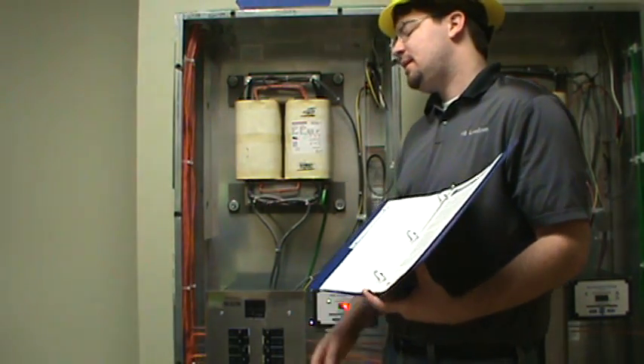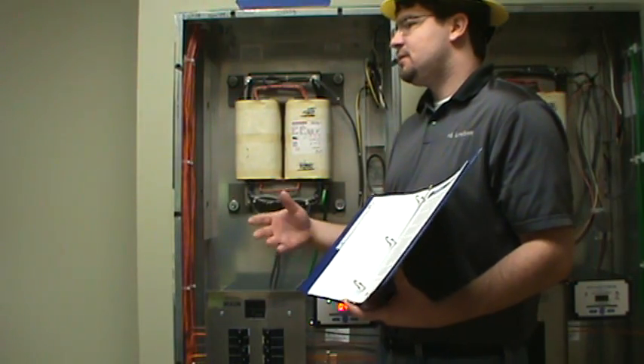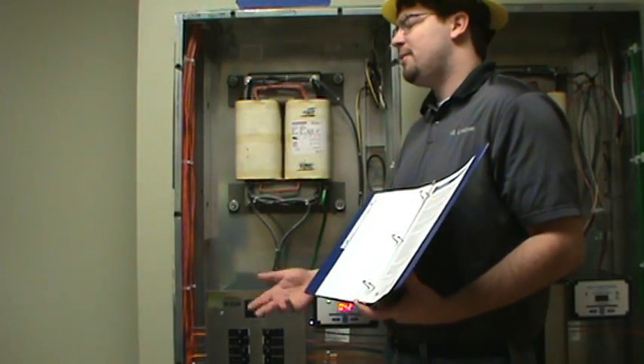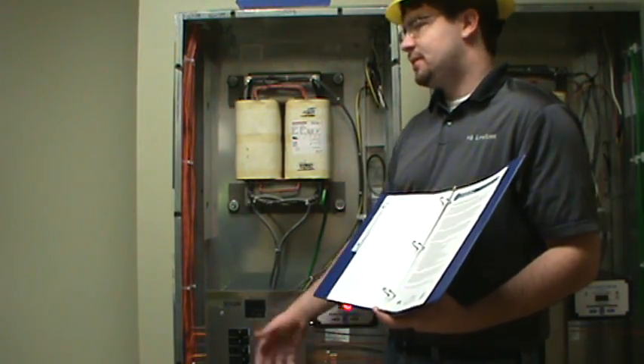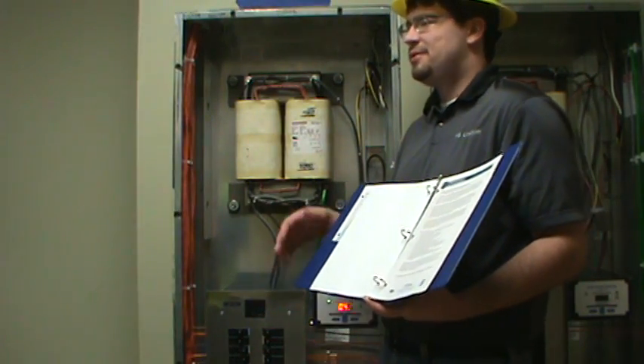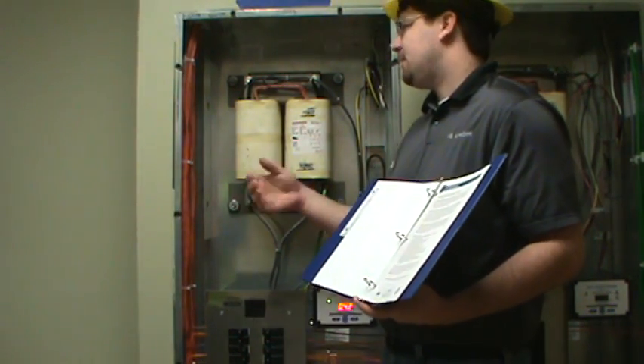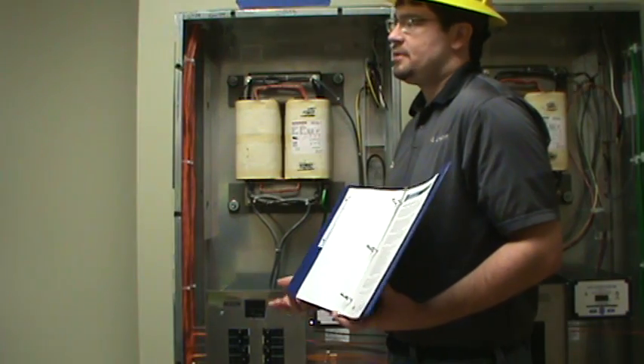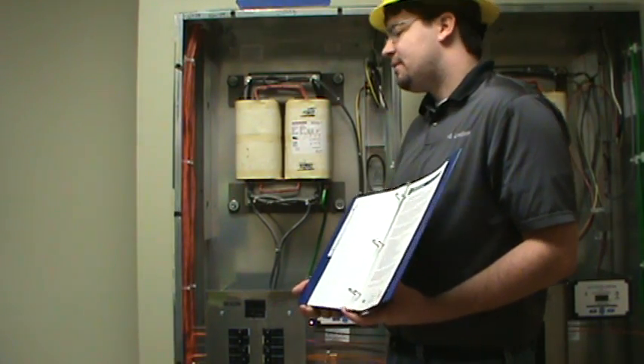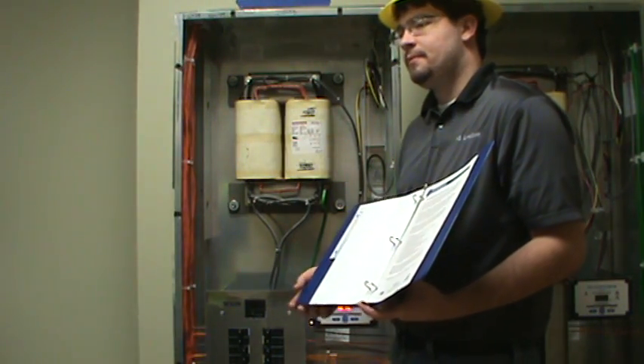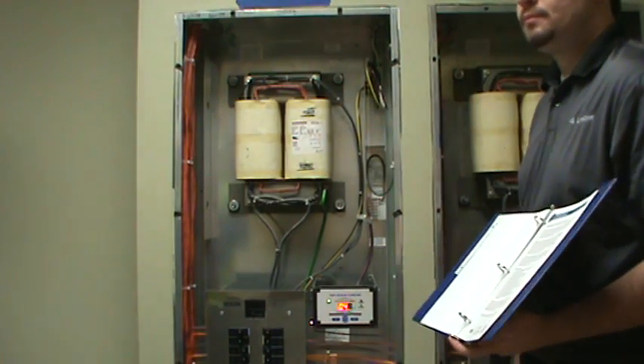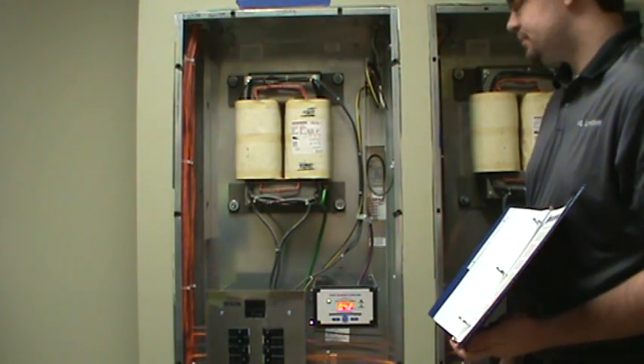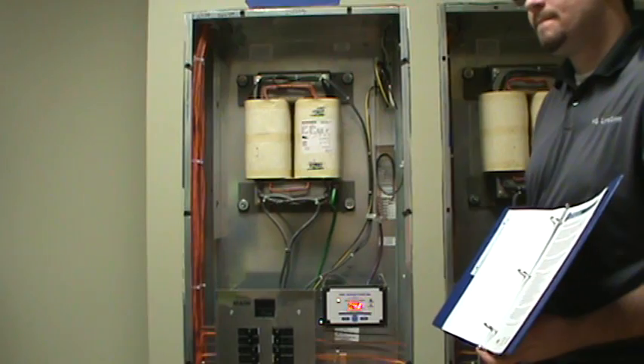What you're actually doing is getting a kind of a source feed, you get a look at what that's like when you turn all those circuits off, seeing if we have any sort of noise coming from our primary feed. That's what you're looking at essentially. Okay. So yeah, I'd say it's still important. So if I had a high milliamp number, I should be able to shut those breakers, and when I shut the breaker that's causing the problem, I should see that number go down?